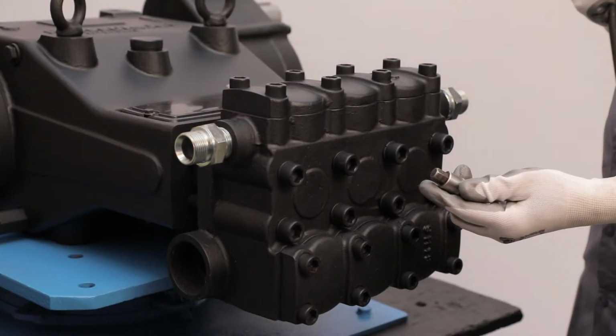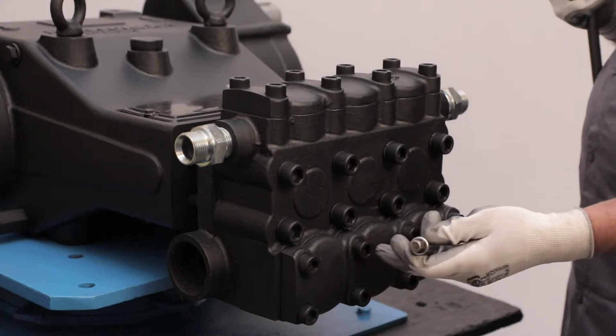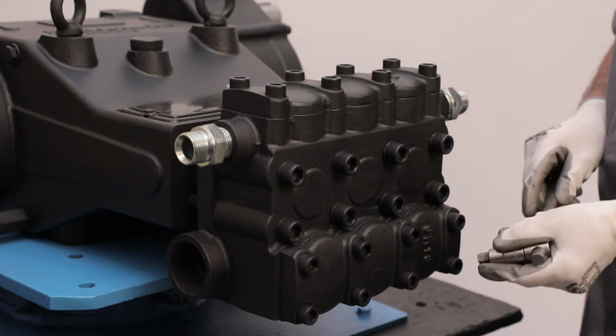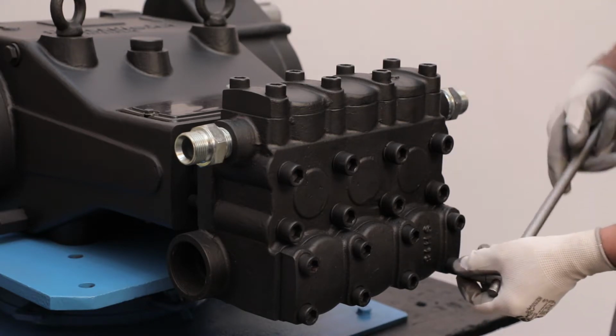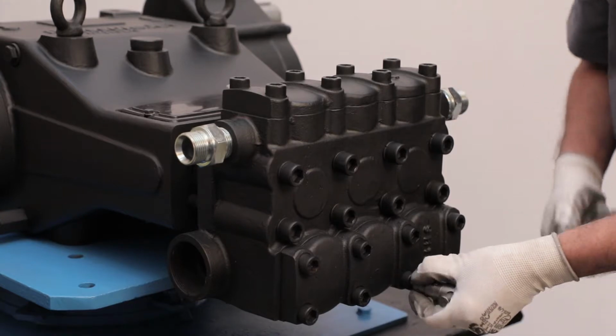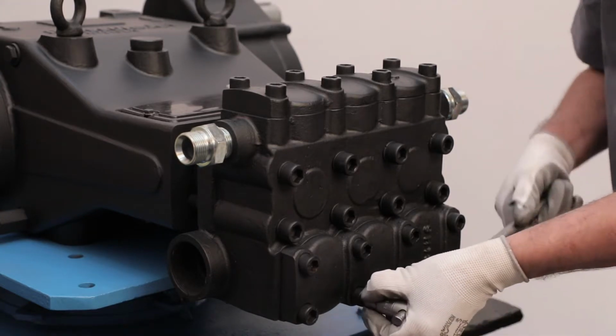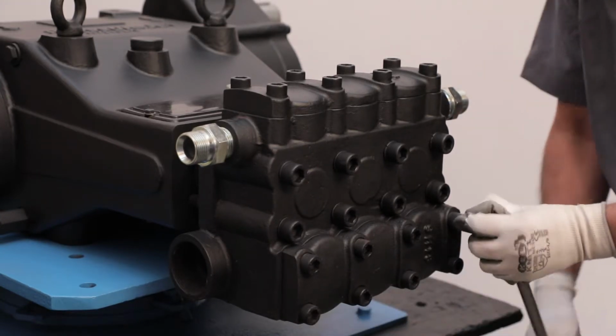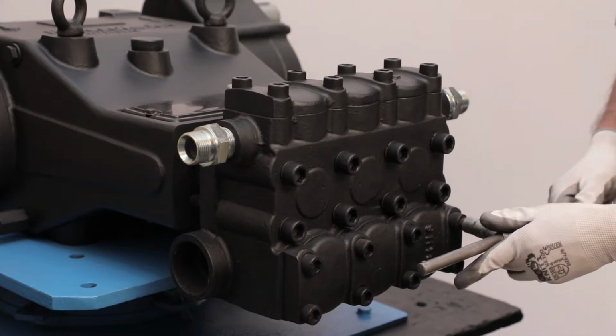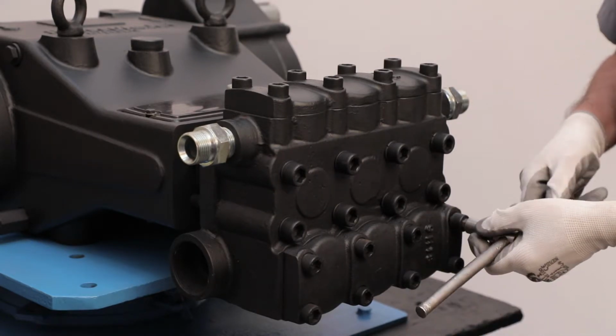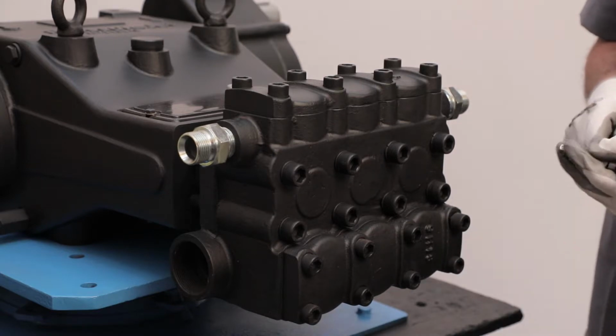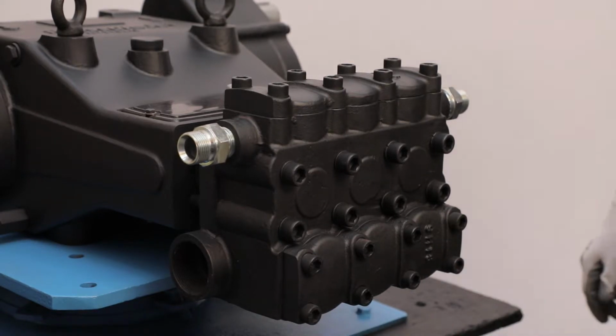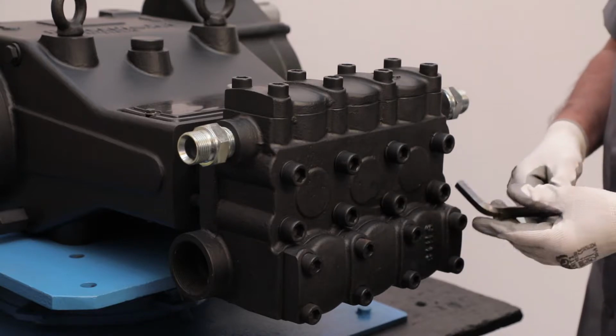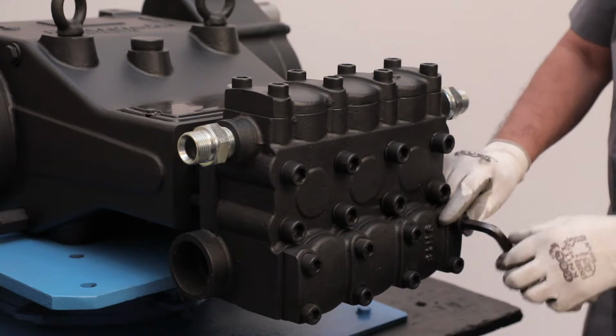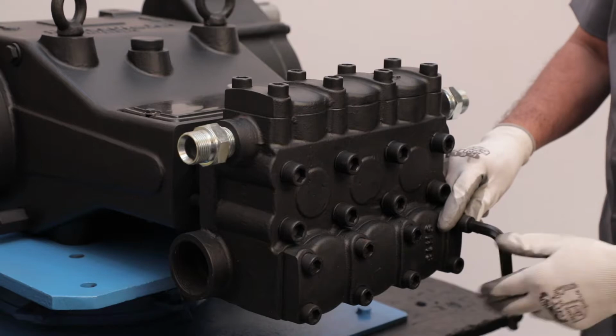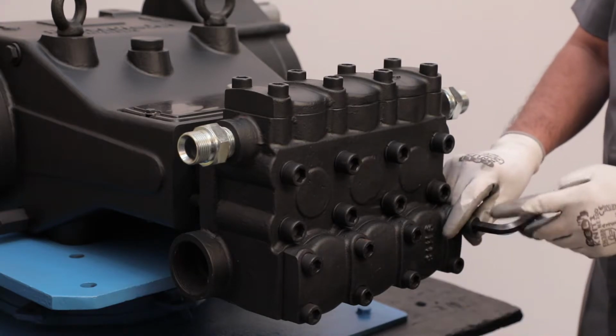First of all, take Allen key socket and wrench and loosen all 8 M16 by 180 cap screws to dismantle suction and discharge valve holder cover. Then, with the Allen key, unscrew all cap screws and separate suction and discharge valve holder cover from the pump head.